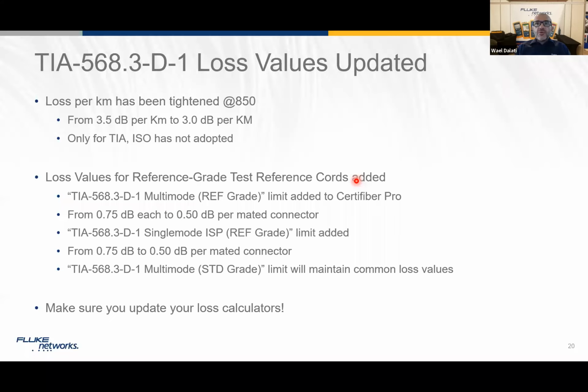Probably not. That's why we always ask technicians and project managers in the field: before you start testing, make sure your equipment is upgraded to the latest firmware, because the latest firmware always carries the latest updates of the standard. If there are changes between the previous firmware and the current one and you are not aware of them, you might get results that are not accurate to the current standard revision. So please make sure you follow that in the right way.